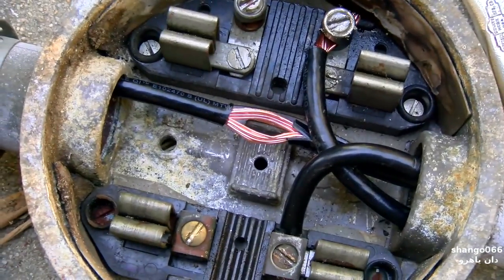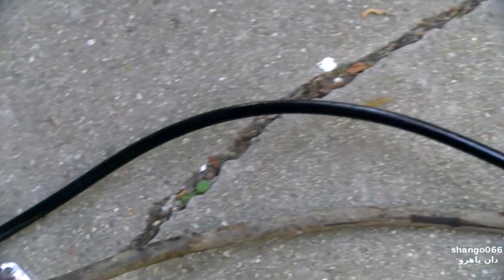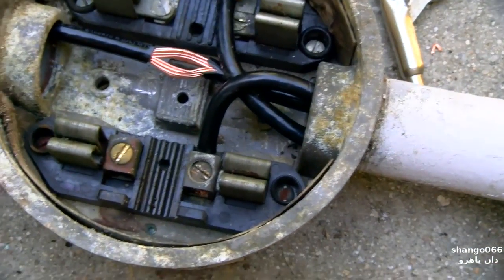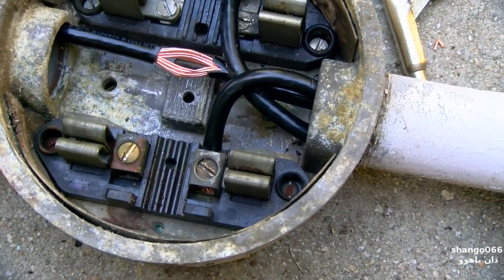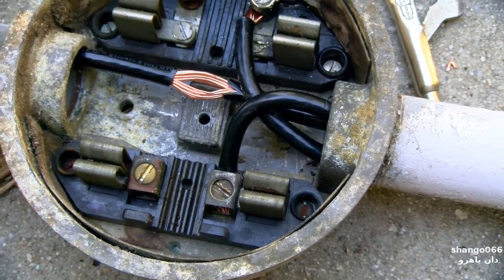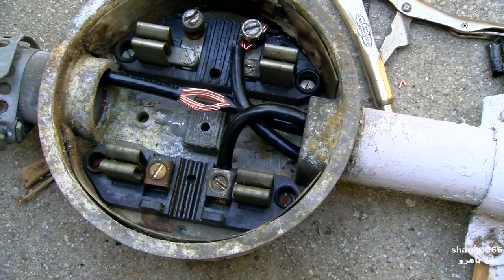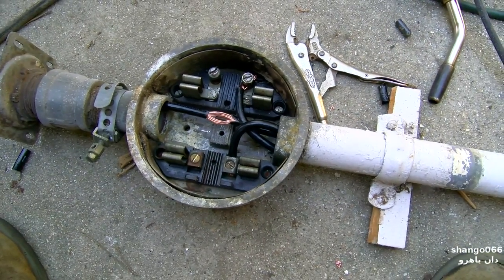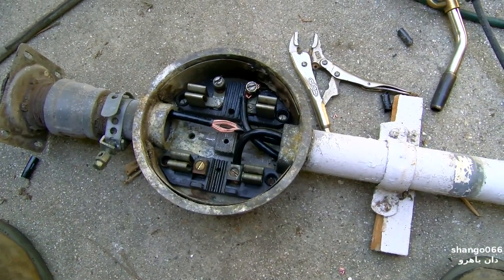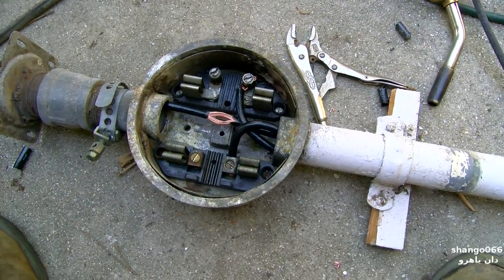See how I've done the neutral here — I didn't actually cut the wire, so the neutral is just going to continue through to the neutral bus bar in the box. This makes sense to me: avoid a splice here, because if the neutral ever goes open, one side of your house — whichever side has the lightest load — is going to float up to 220 volts. A good solid neutral is very important.